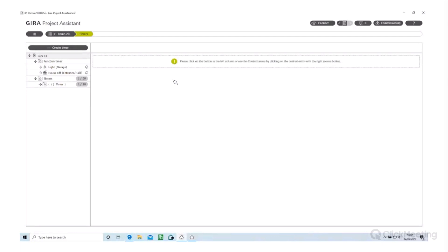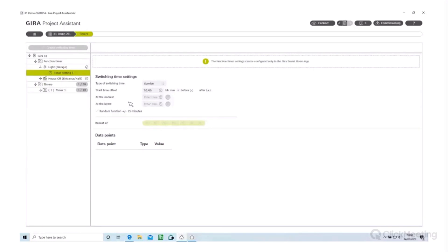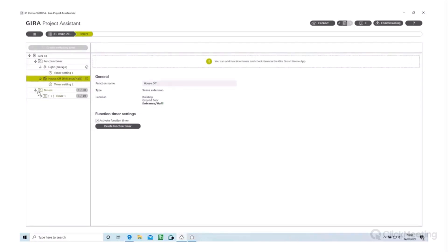In the timers view there are now two types. We have GPA system timers for programming - the ones the user has no access to, things happening at a system level. And we now have function timers, which are ones added via the app. From here we can delete them and activate or deactivate them, but we can't actually change the timing - those settings are grayed out and are only set via the app. It makes it easy to see what the customer has set up.